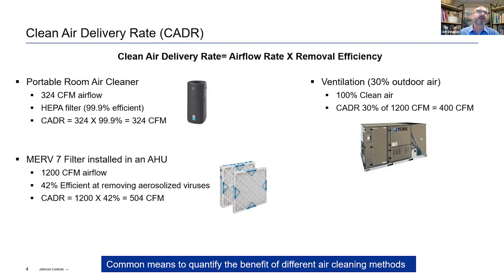On the upper left-hand side, we have a portable room air cleaner. This one moves 324 CFM of airflow. It has a HEPA filter in it, so it's 99.9% efficient at COVID-sized particles. If you multiply the two together, you get about 324 CFM of clean air delivered to the space. You can compare that to ventilation. This is a rooftop unit. This one's set up with 30% outside air. In the context of COVID and COVID-laden particles, we're going to assume that the outside air is 100% COVID-free, so 100% clean air. So if you take that 30% outside air times the 1200 CFM of a 3-ton rooftop unit, you get about 400 CFM of clean air coming from that ventilation system.